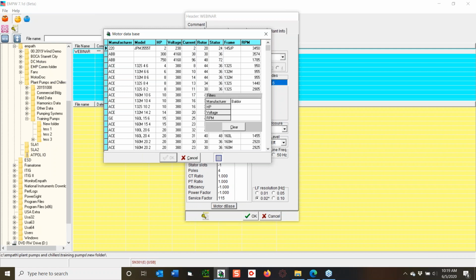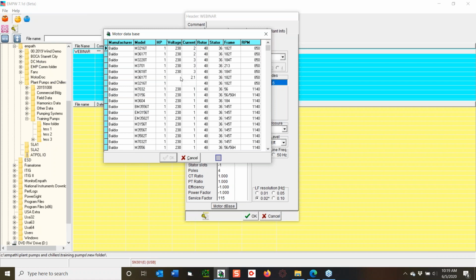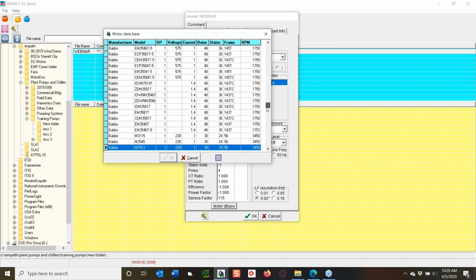Now, because it's a 600 horsepower, 460 volt motor, I don't know if that's what I'm going to get, so I hit enter, by the way, and I get that. Now I can get this out of the way, and I can scroll down through these until I get around a horsepower I'm interested in. It's a Baldor, so there's a lot. Here we go - so when I start down here, I also want to look at the RPM.